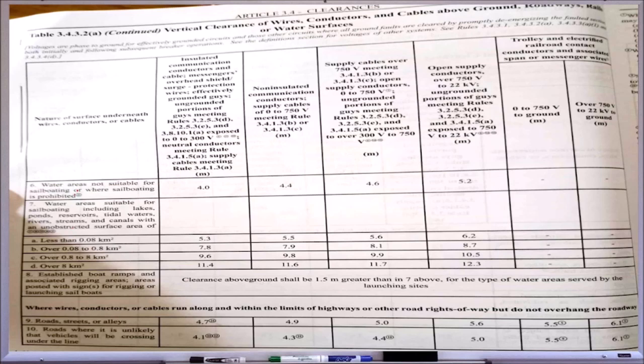So water areas not suitable for sailboating, or where sailboating is prohibited, 4.0. Pero pag merong mga pwedeng dumaan na mga barko or mga maliliit na sasakyang pandagat, iba na yung kaniyang clearance. So pataas na siya ng konti, depending on less than 0.08 kilometer square the area na dadaanan ng ating wires. Where wires, conductors, or cables run along within the limits of highways or other roadways but do not overhang the roadway. Ito din.